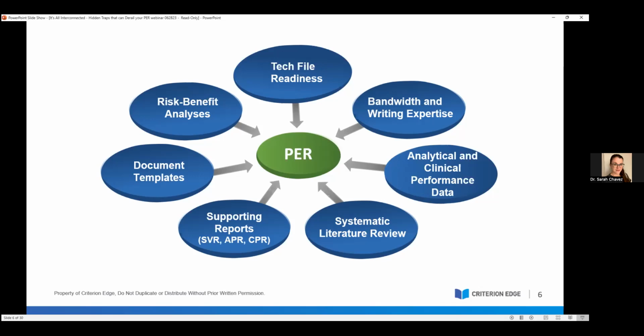And then finally, these supporting reports. These are really the black box here for many of us. Because in the medical device world, these separate reports are not a requirement. And so the supporting reports are built upon extensive literature searches and many other supporting documents that are going to separate the data into the data that supports the scientific validity of your approach, and the association of that analyte with the clinical condition or physiological state.